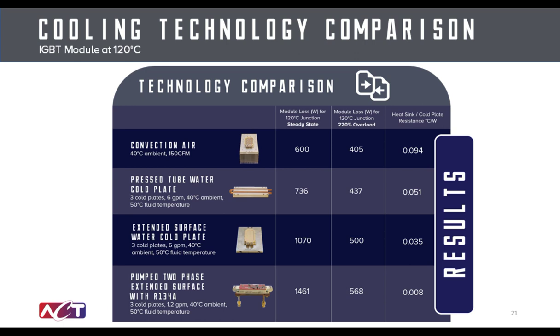Next, we'd like to show a comparison of how pump two-phase cooling compares to more traditional cooling methods for a power electronics application. In this case, we have an IGBT module that needs to maintain a temperature below 120 degrees C. As you can see in the chart, 4 cases were examined: a conventional air-cooled heatsink, a traditional copper tube aluminum plate liquid cold plate, an extended surface liquid cold plate, and a custom-designed pump two-phase cold plate.